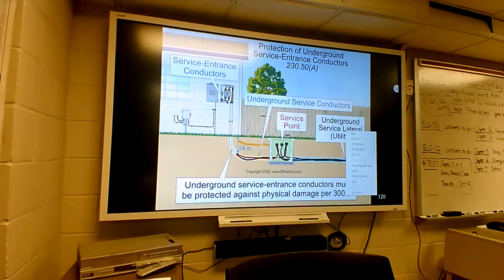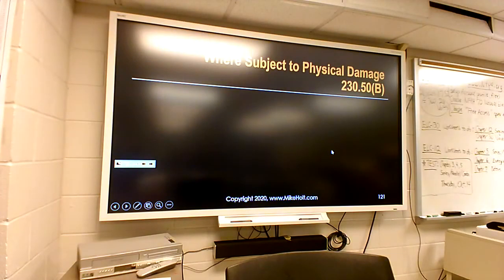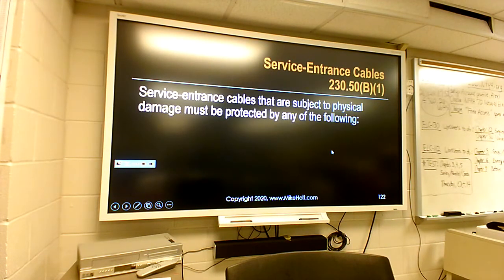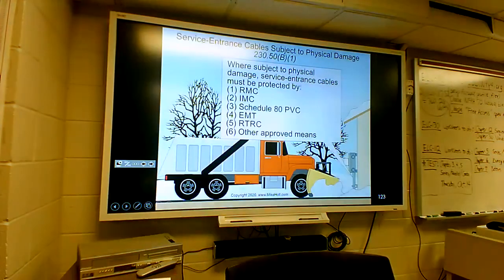Yeah, it's on page 335. That table is telling you the depth, how far down you got to dig when you do underground wiring. Okay, so that's what they're referring to there for protection. Where it's subject to physical damage, you got to protect it by one of these methods here. Now here is where you got a snow plow here that could hit that conduit. So you got to have it definitely in conduit for sure.